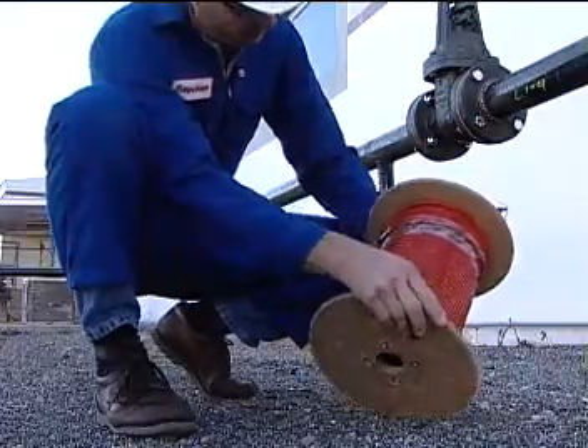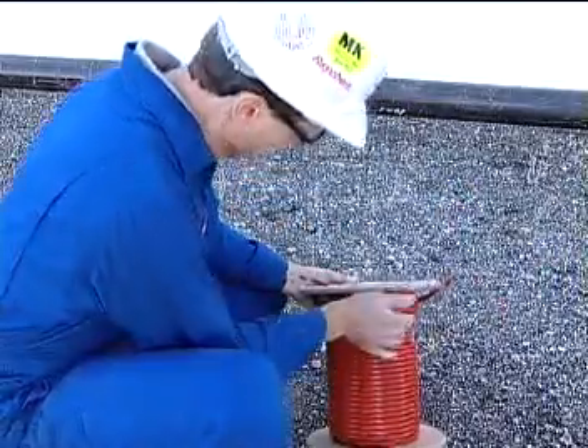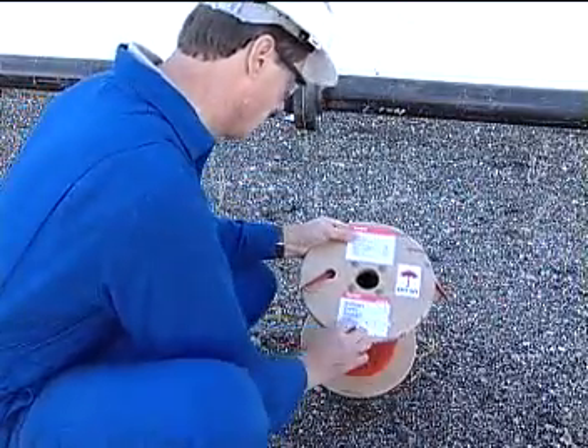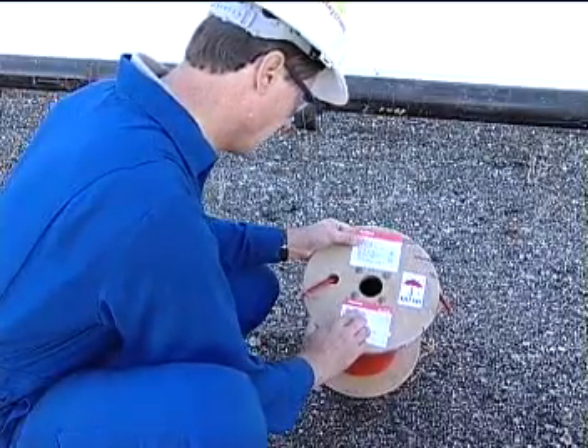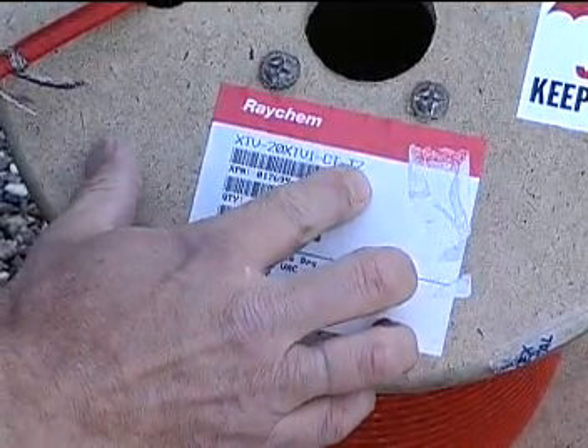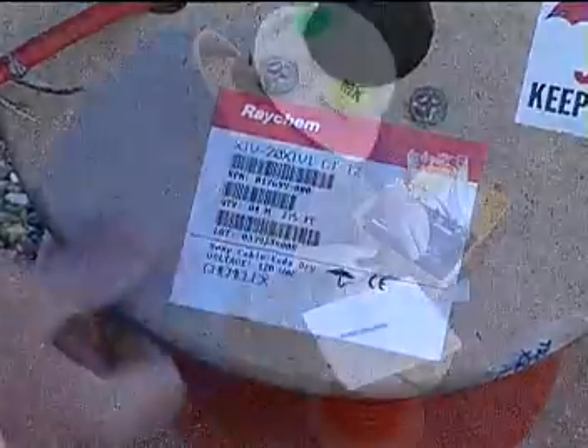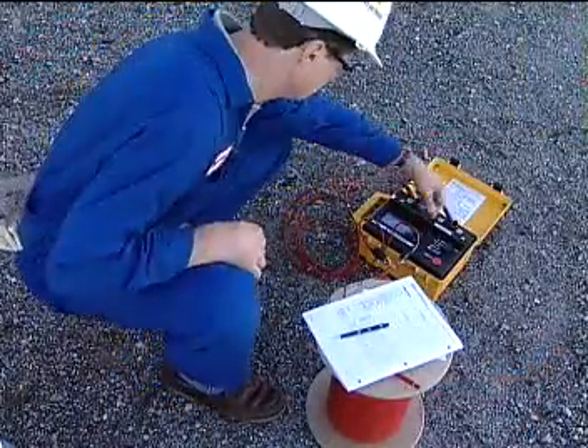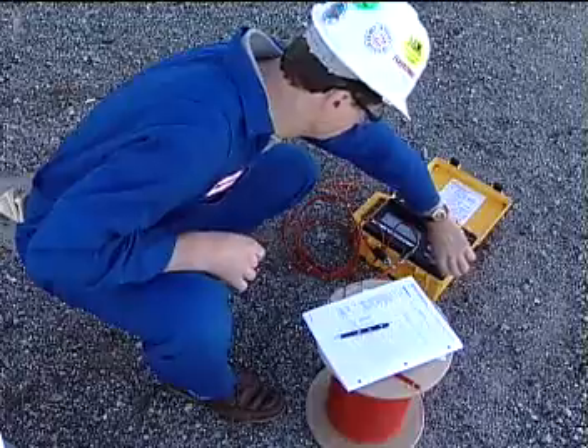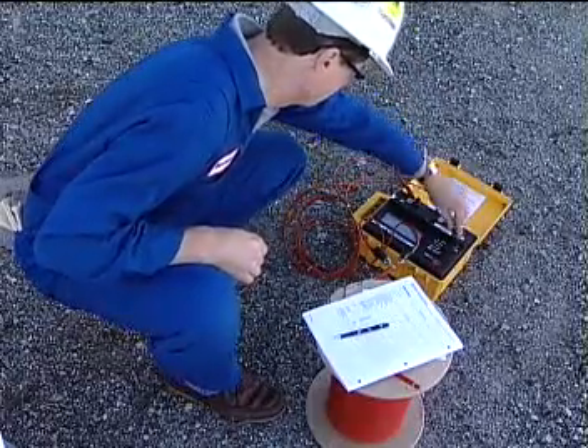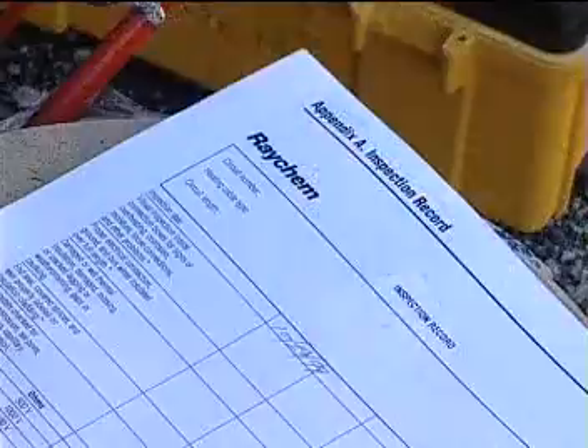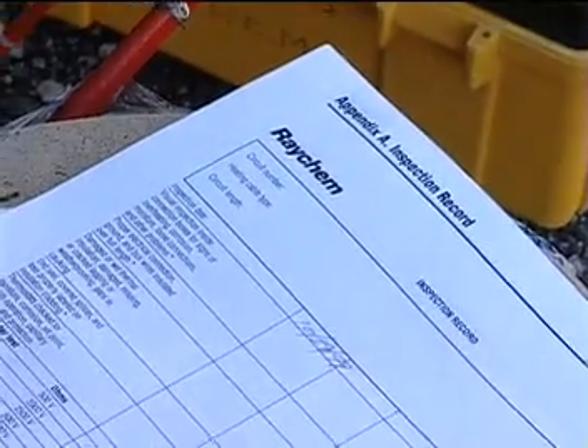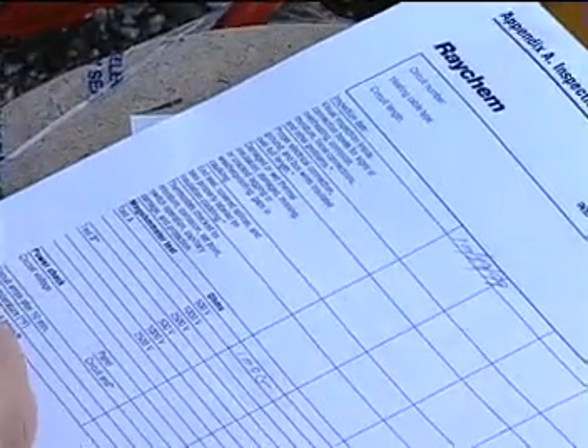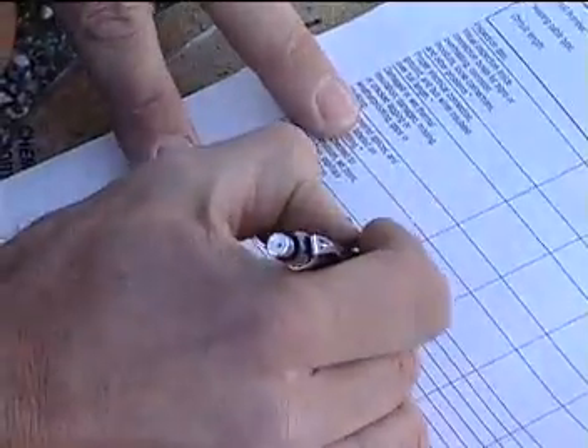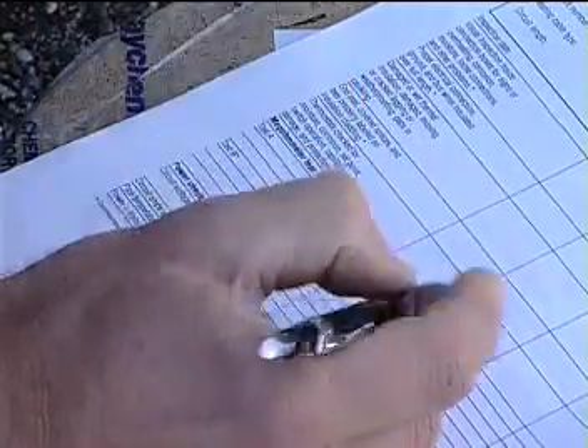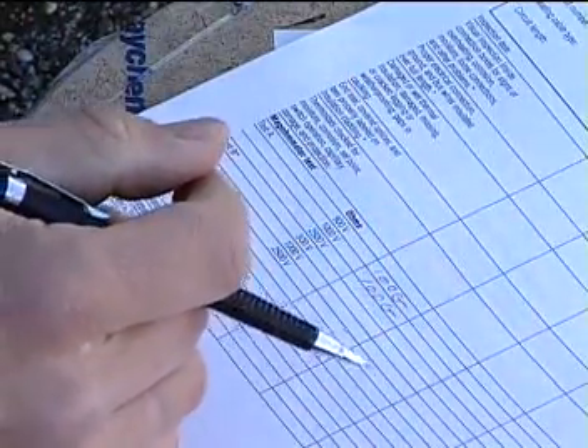Also, only Raychem-approved components should be used. Substitutions negate agency approvals for the entire heat tracing system. Be sure to check that you have the correct heater cable for the application. Then, conduct an insulation resistance test while the cable is still on the reel. It should register greater than 1,000 megohms at 2,500 volts DC. Record this and all subsequent circuit readings in the installation and maintenance guide. Carefully following these steps prior to installing the heating cable should help eliminate many problems.